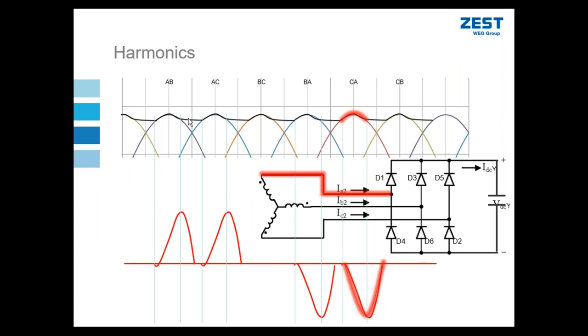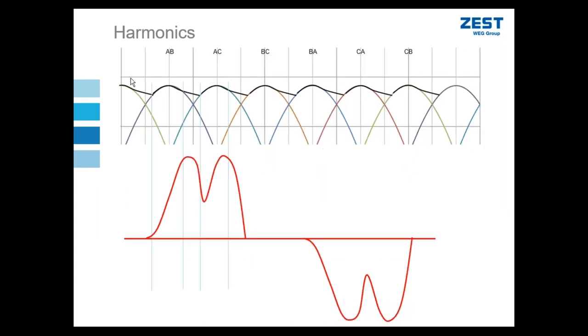Conversely, when my load is very heavy on my motor, when I'm operating in a full load condition, I draw the energy from the capacitor down much more rapidly. And so it reduces the amount of time that I'm drawing energy from the capacitor and increases the amount of time I'm drawing energy from the supply. Just to demonstrate that visually, this is an example. So you can see here, my capacitor drawdown on a heavy load situation is much greater. And so you can see I no longer have two separate peaks. I now have a more continuous voltage waveform under a heavy load condition.